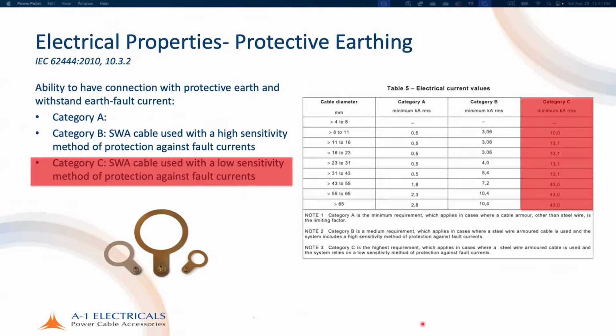If you run a separate GI connection, what is the resistance? Is there a product standard for that GI that is running separately? No. Only for the GI that is part of the gland that is covered under the cable standard. So absolutely, you can use an armor for a gland for a protective conductor as long as you use it with the correct gland. It is dimensionally compatible. It is a dedicated PE conductor. And IS 732 perfect, there's no objection to this.